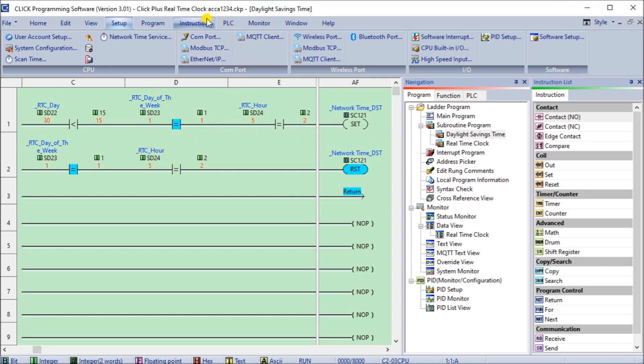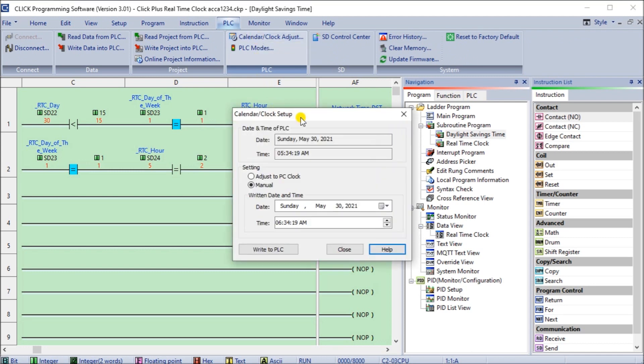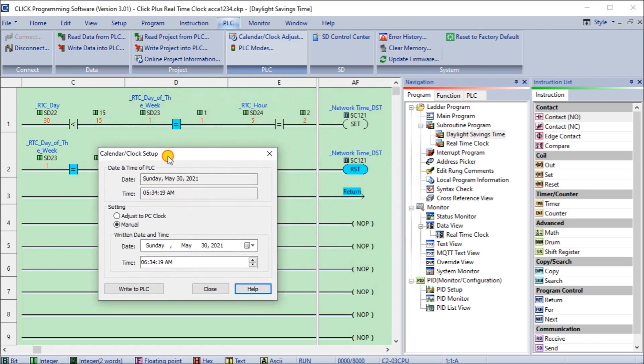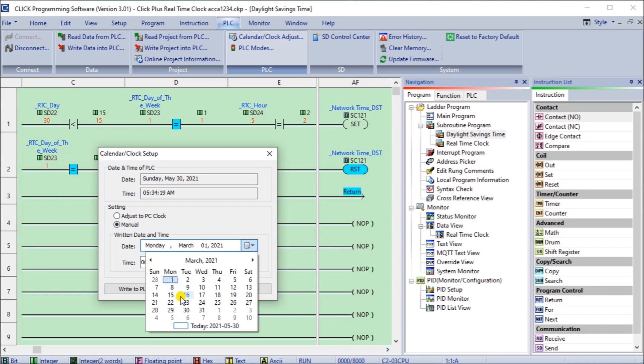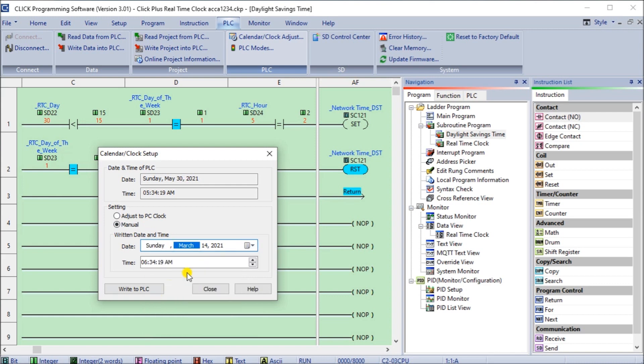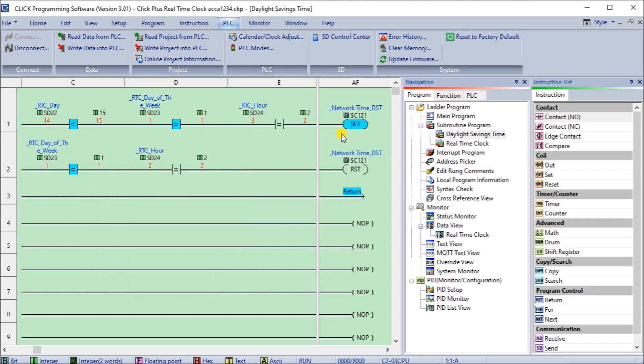So let's go and set that manually. Go to PLC, calendar clock adjustment, and on our adjustment what we will do is change this date, and we will actually say it's going to be March and we're going to put in March 14th which is the second Sunday, and our time we're going to put in 1:59 and 55 to allow for five seconds, and then we'll write that to the PLC.